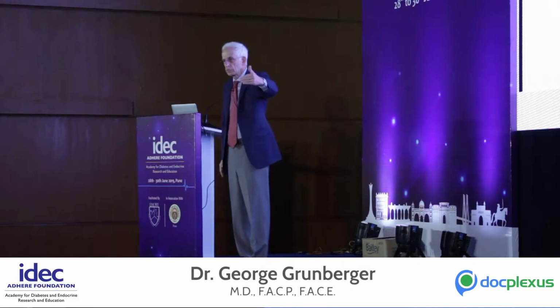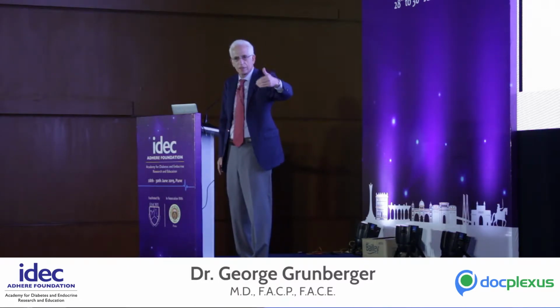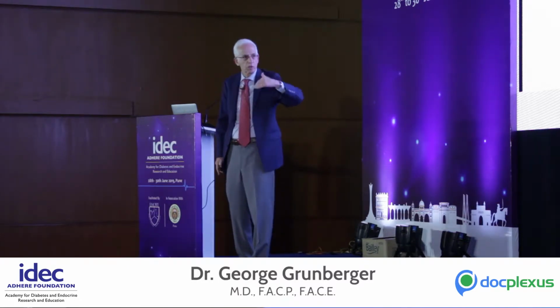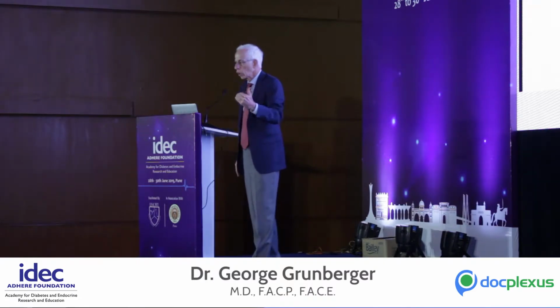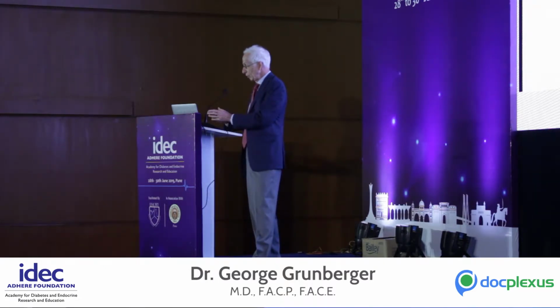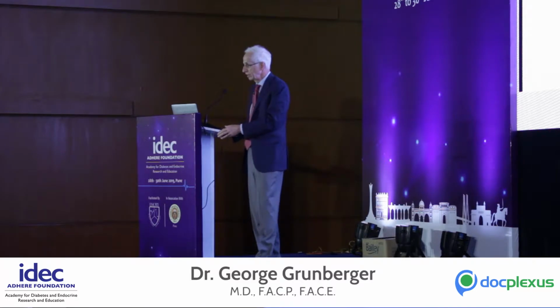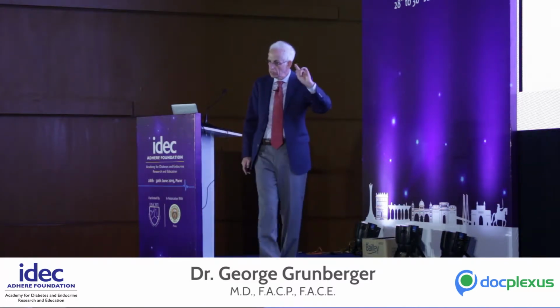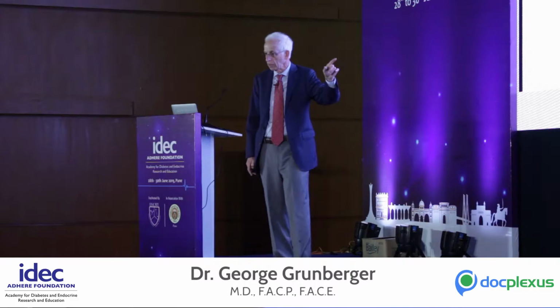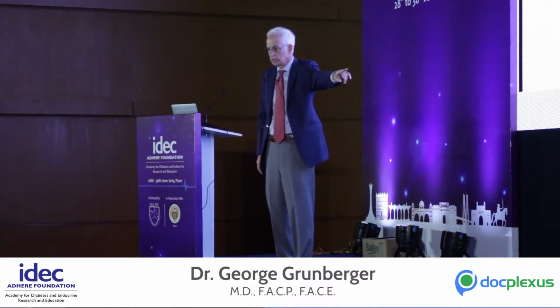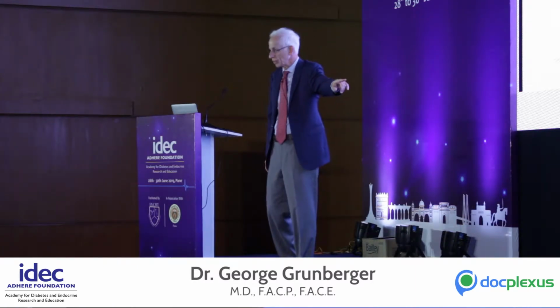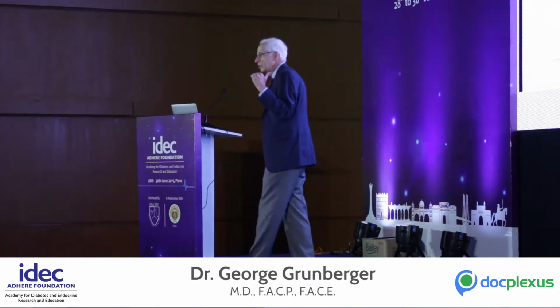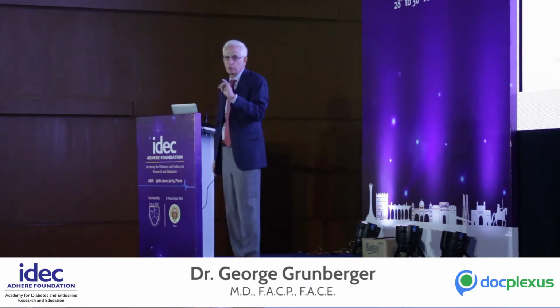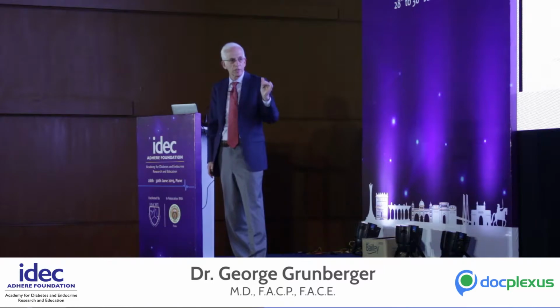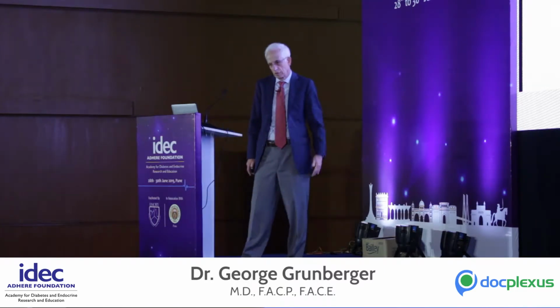And it has features, because remember what I said, that this thing can actually predict what's going to happen because you see the rates of change. So not only do you get an alarm when you have a hypoglycemic reading, it can predict and will give you a signal, alert, and alarm: you're about to be hypoglycemic in the next 15 minutes, do something. This is also the first device which doesn't have interference from acetaminophen, because the other ones did. And so there is no influence there.